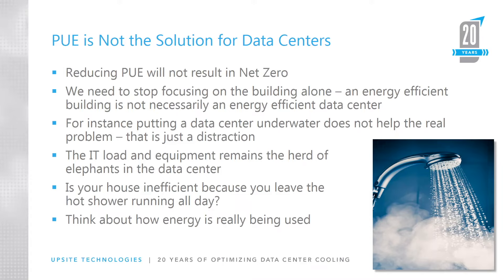An energy-efficient building with a low PUE is not necessarily an efficient data center. If you've got a data center with a very low PUE but the IT load is just spinning doing nothing, that's hugely inefficient — it's serving no useful purpose. And putting a data center underwater is a marketing gimmick. Yes, you're achieving good cooling, but you're still consuming the same power on the IT side — nothing has been done to reduce IT energy consumption. The IT load remains not just an elephant in the data center, it's a herd of elephants. The more we focus on PUE, the less we are able to get a handle on the IT element.